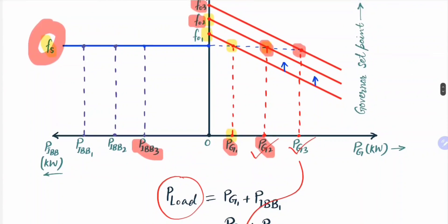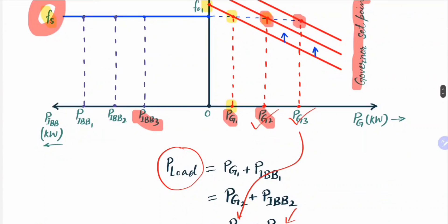So we can conclude that by increasing mechanical input to the alternator — by increasing the governor set point — the no-load frequency of the alternator will shift up, supplying more and more active power to the nearby load or to the infinite bus bar. If the active power supplied by this alternator exceeds the load demand, the excess power will flow back into the infinite bus bar, since the infinite bus bar may consume or supply any amount of power without a change in frequency or voltage.